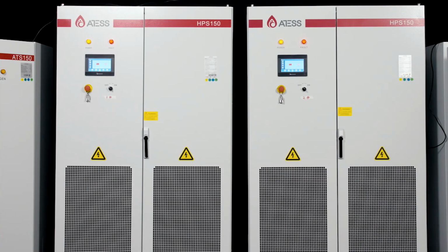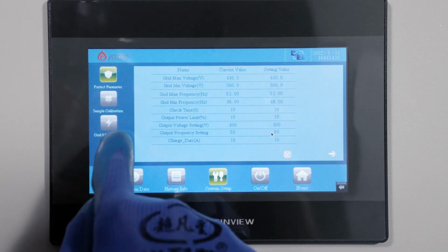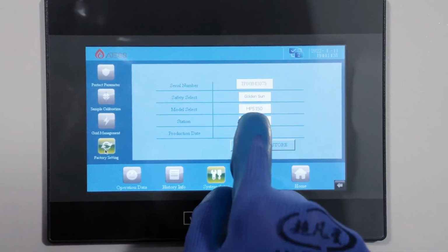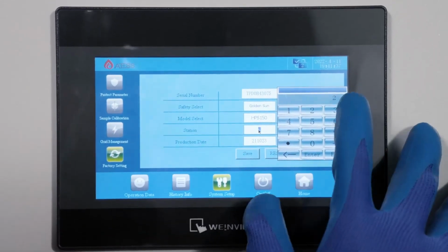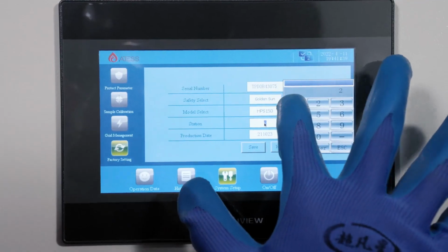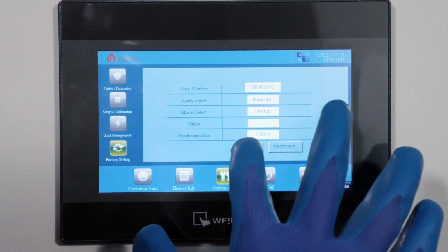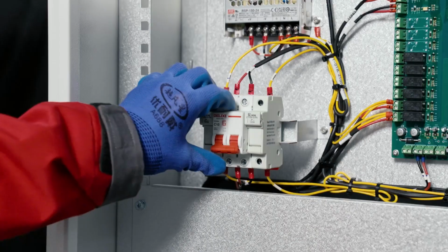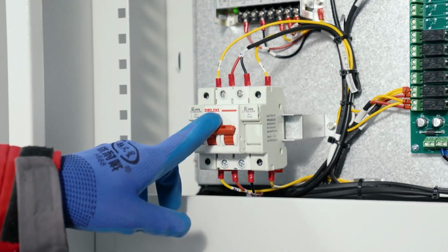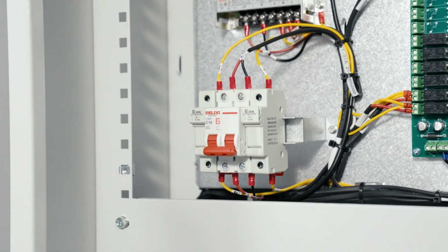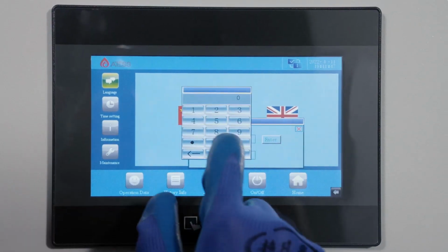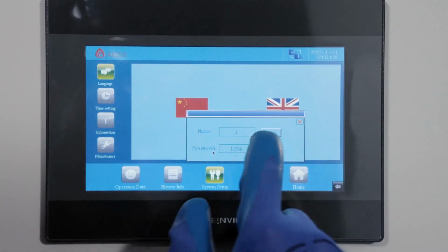Configure the 2 HPS stations. Set number 1 HPS to 1, click Save, and number 2 HPS to 2, click Save. The setting value will be displayed in the upper right corner of the screen. Close the power breaker of the number 1 ATESS and disconnect the power breaker of the number 2 ATESS. Set the login password to login number 1 HPS.